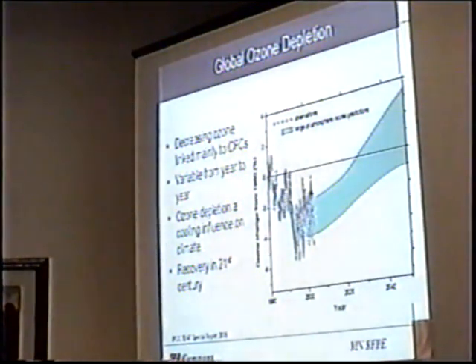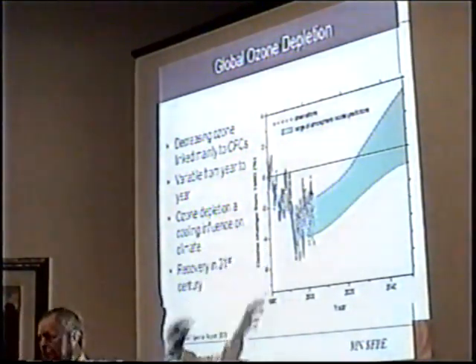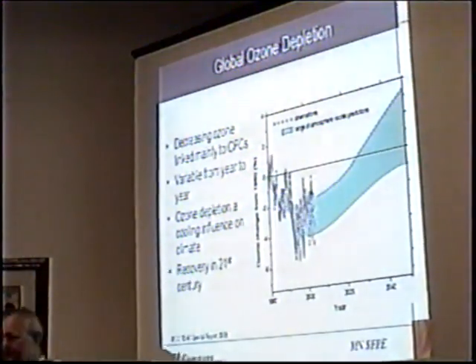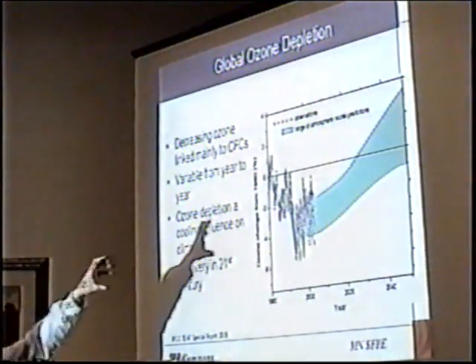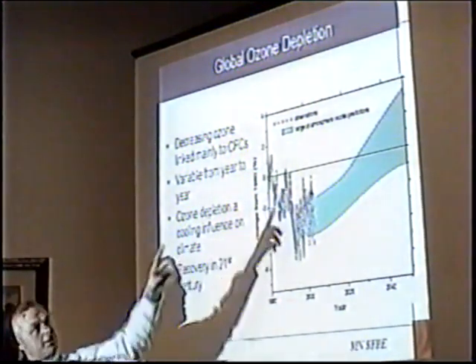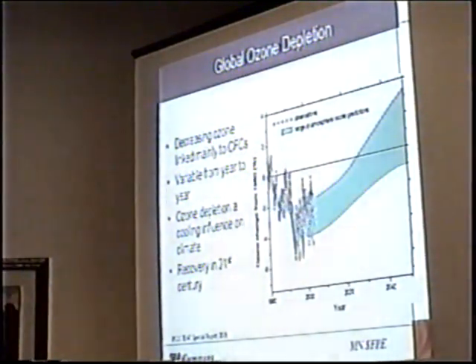Basically, we've gone through this process for 20 years, and this graph shows that ozone depletion was significant until we banned it in 1987. It started to make a comeback once we stopped putting CFCs and halons into the atmosphere, and now we predict that by mid-century the ozone will be back to normal. But wasn't that basically Freon and not halon? Yes. 95% of all the halon ever produced is still in systems. We'll talk about that in a second, because they found 15% of the problem was halon, because halon is much more aggressive at depleting the ozone than the CFCs, on the order of magnitude more effective.